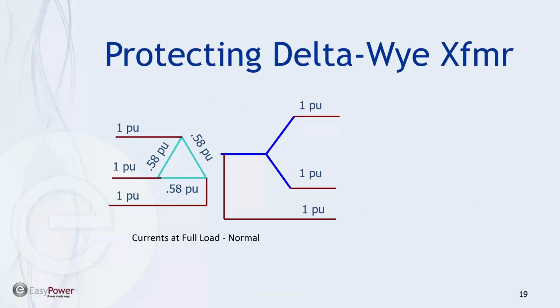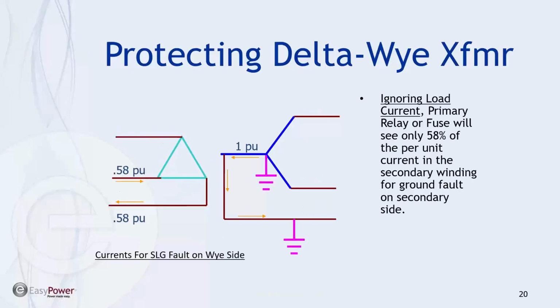So in normal operations at full load on the Y side, if we're measuring 1 per unit current, it corresponds, at least in magnitude, per the turns ratio to the 1 per unit on the primary side. But it's not a direct correlation. It's because we have 2 phases involved, and each one is 0.58. So my total per phase is going to be a 1 per unit that corresponds again to the turns ratio in the secondary. Now that's all well and good if we're talking about 3-phase faults.